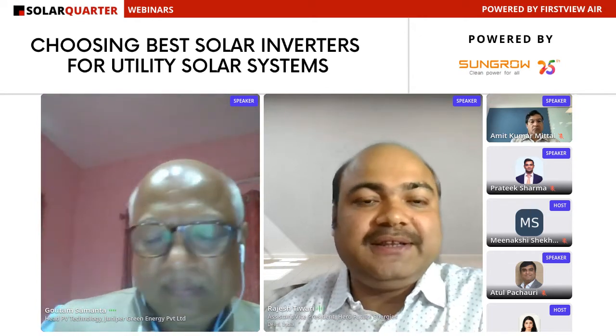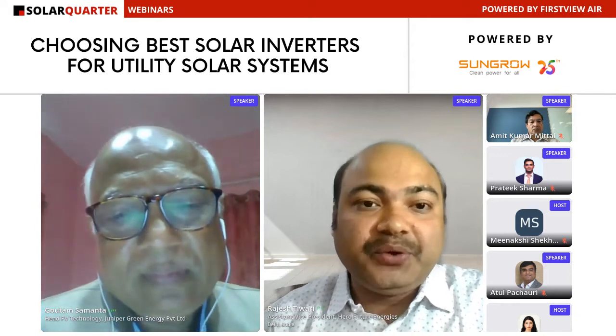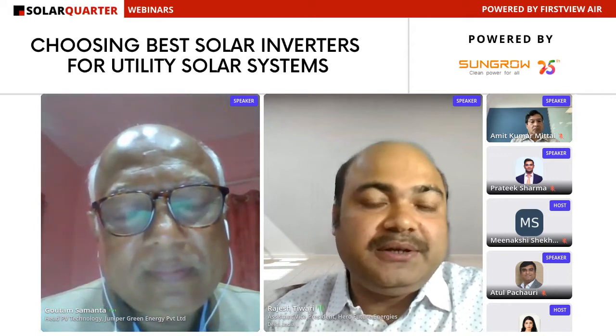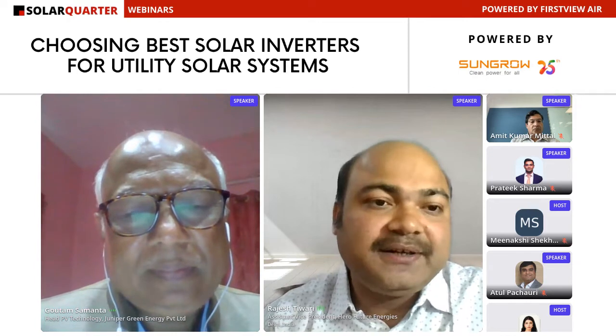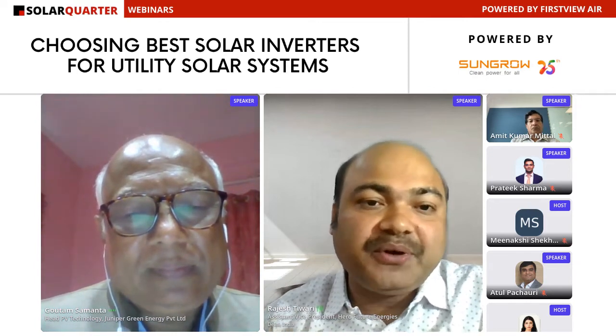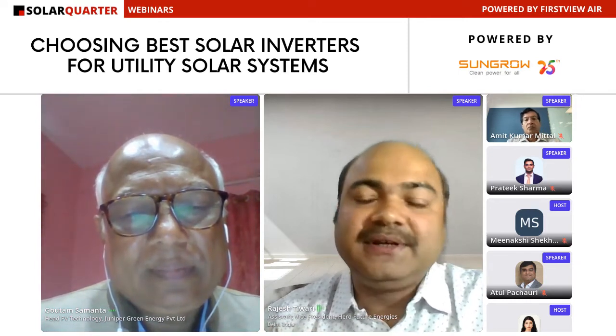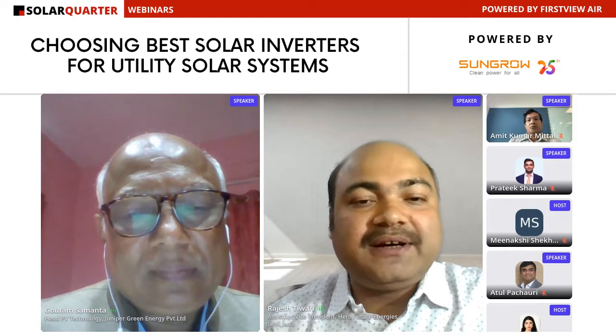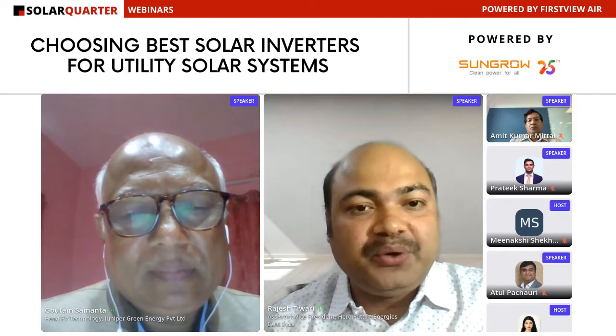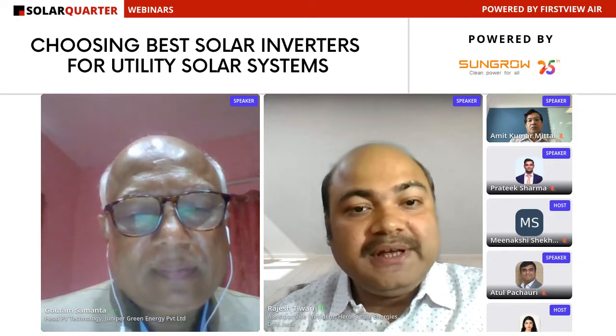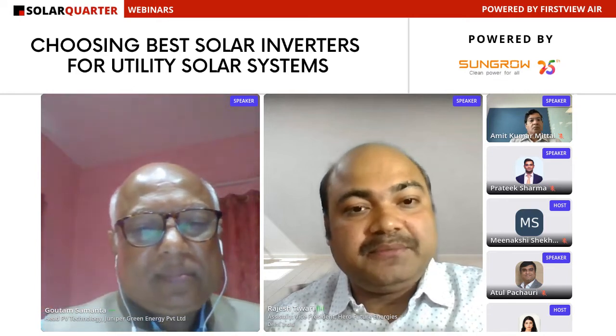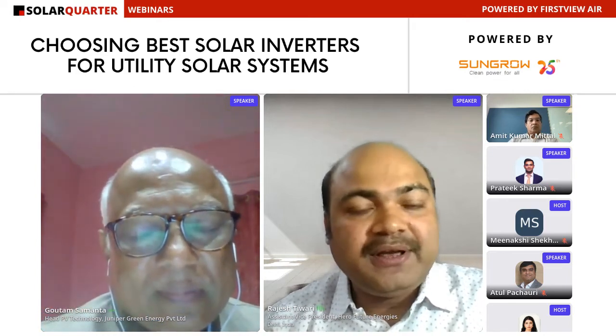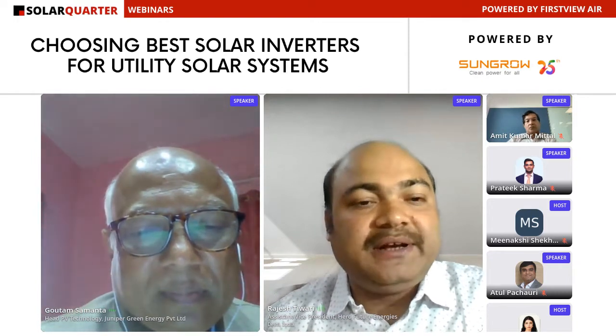So you are in the range where you can use a Y connector and save on your DC string cables. But with the 17 ampere low voltage modules, when you add the albedo gain, you will reach nearly 19 to 20 ampere, so there will be a difficulty.